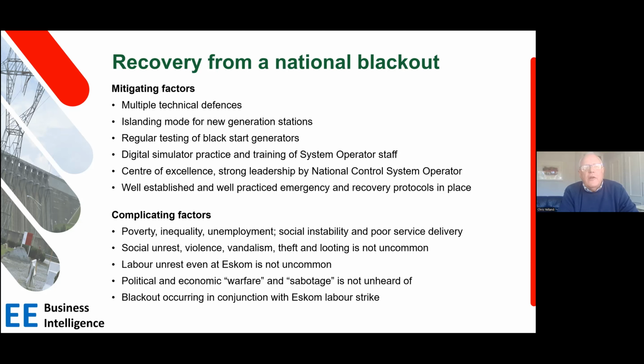Eskom do regular testing of black start generators. They have a certain number of black start generators, 3 or 4, and test them regularly. One of the black start generators is the pump storage schemes - you have water at the top dam and the bottom dam, and they never allow the top dam to run empty. They keep about 20% of the water in reserve just in case it's needed for a black start, so that hydropower can restart the plant quickly, within an hour or even quicker if there's water in the top dam.